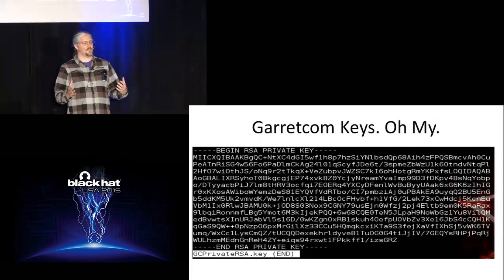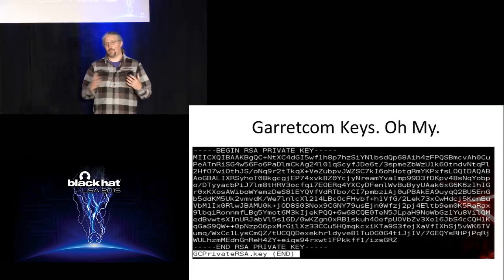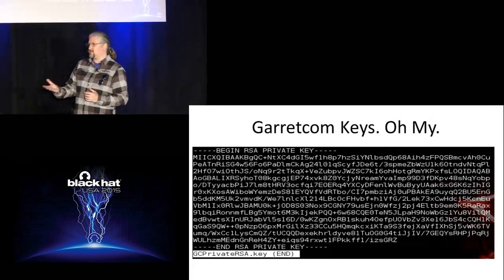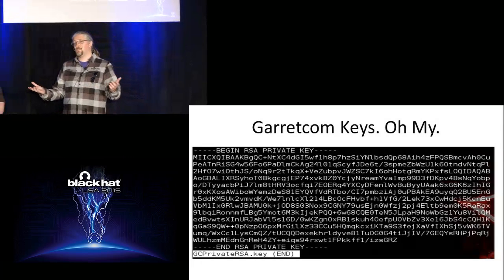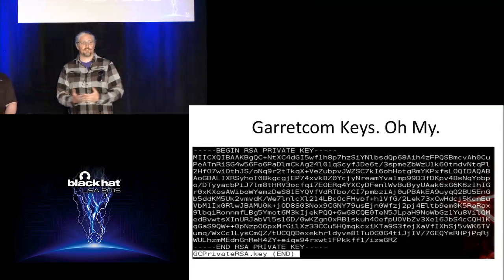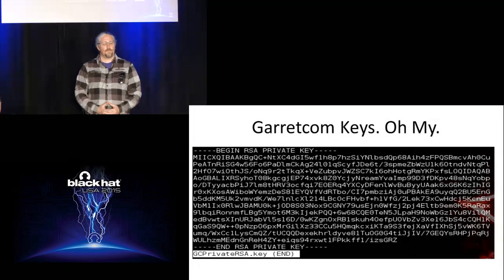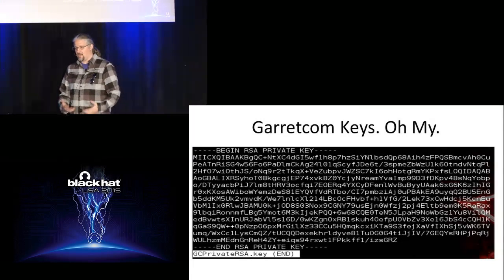And this led to a position where we didn't get any patches for the firmware for these devices for 8 months, right? Which is a particularly long period, especially when you consider in ICS environments, people can take a year, 2, 3 years to patch because you can't afford to bring the process down to replace your switches, right? And this is your network. This is carrying all your process data.